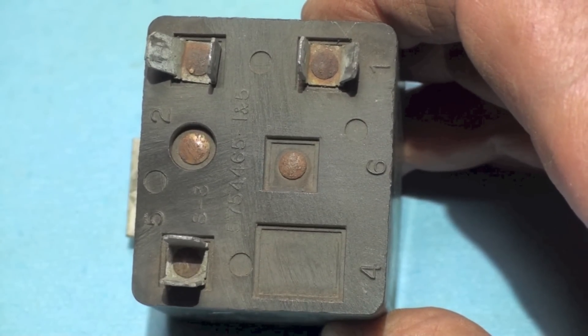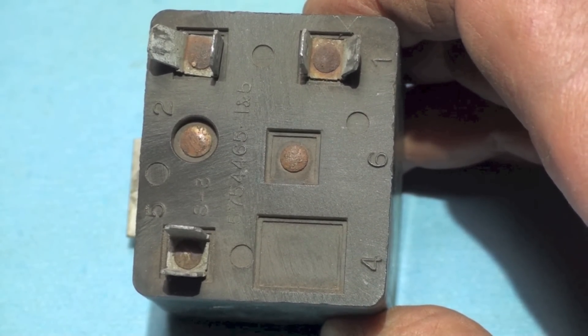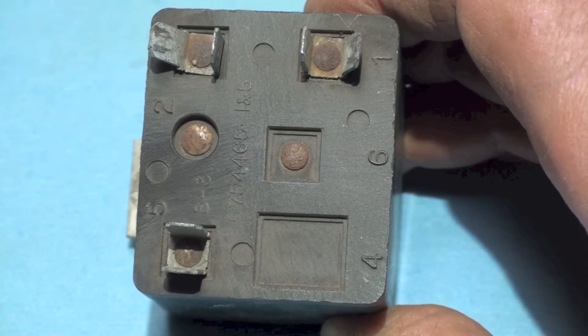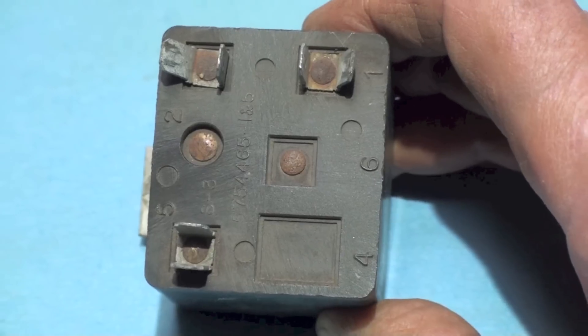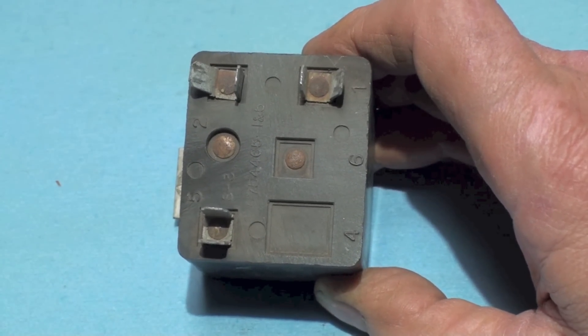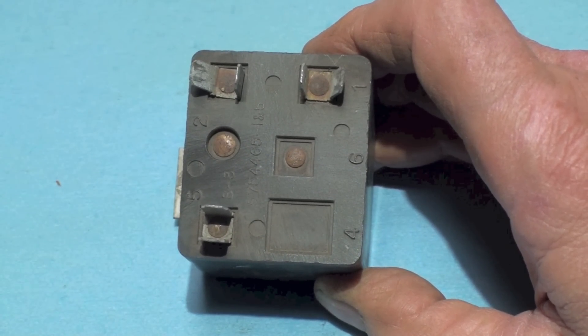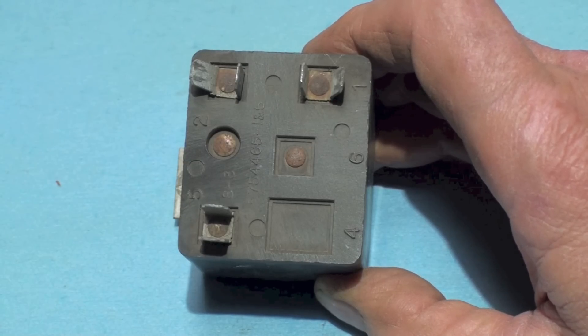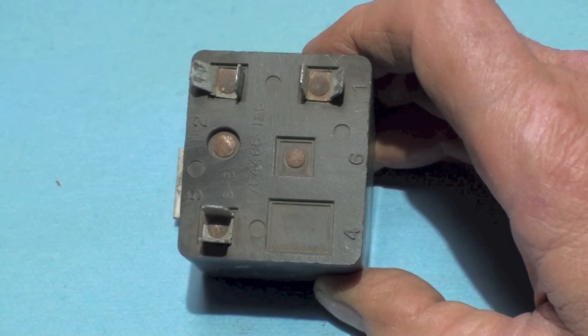Now this is a normally closed relay that energizes using back EMF, so it's a little bit of an odd duck but it works really good. Under normal conditions, the switch will be closed when the compressor starts and that'll have the start winding energized.